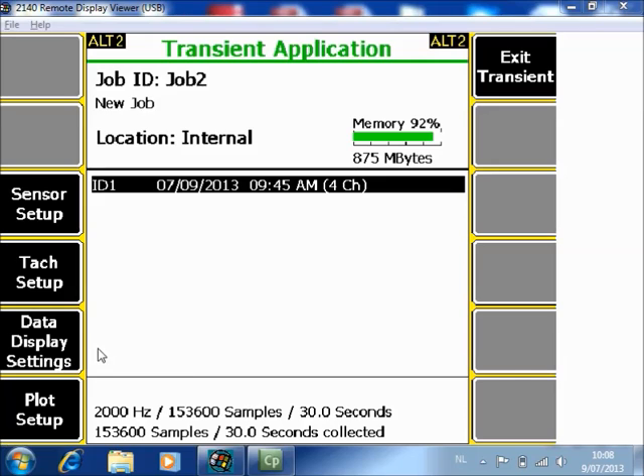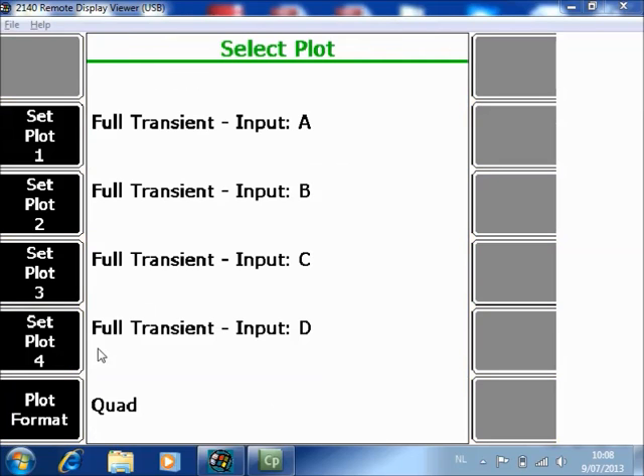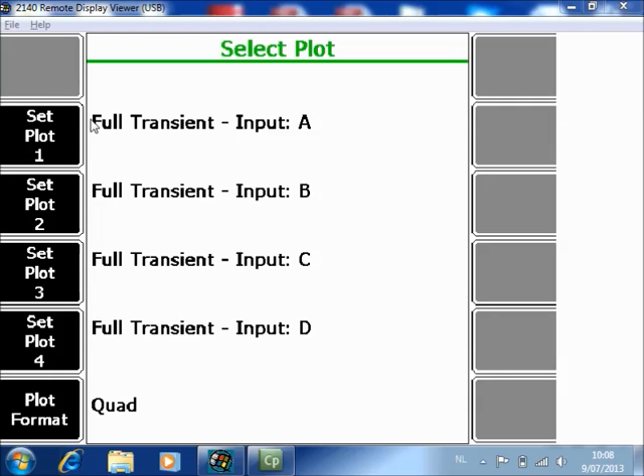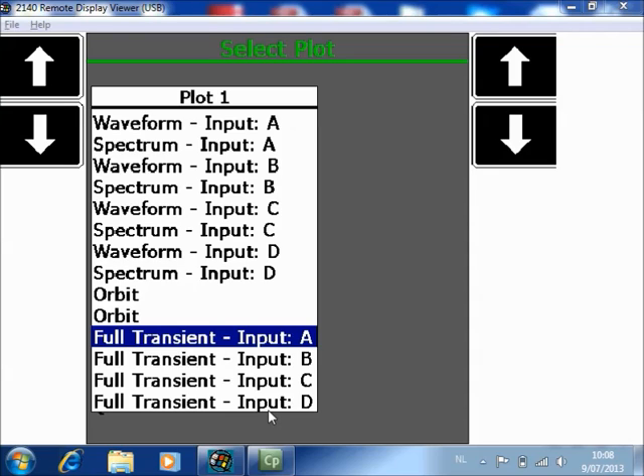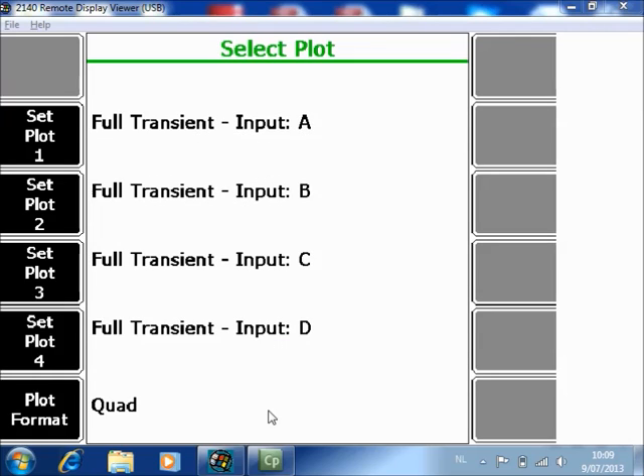In plot setup, you simply specify what kind of plots you want to see after collecting the data. You have a maximum of 4 plots. I only show plot 1, so I click on F2. Here you can choose between waveform A, spectrum A or B, C or D. You can have the 2 orbits or the full transient. In this application, after collecting the data, I want to see the full raw transient data on the 4 channels. So my personal preference is to have the 4 transients active here, and I prefer the format quad.